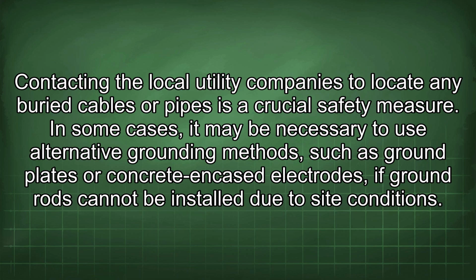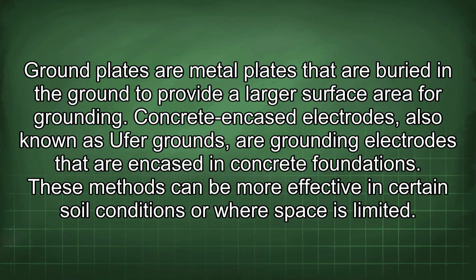In some cases, it may be necessary to use alternative grounding methods such as ground plates or concrete-encased electrodes if ground rods cannot be installed due to site conditions. Ground plates are metal plates that are buried in the ground to provide a larger surface area for grounding. Concrete-encased electrodes, also known as UFER grounds, are grounding electrodes that are encased in concrete foundations. These methods can be more effective in certain soil conditions or where space is limited.